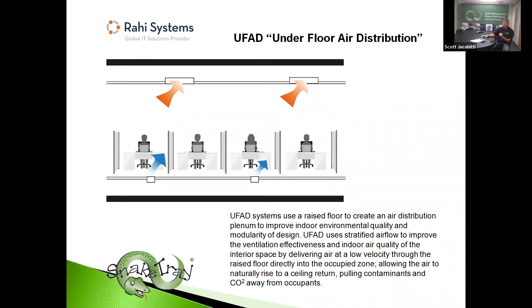The sustainability of an underfloor air delivery system improves energy efficiency. In the old way, I'm pumping high pressure cool air, say 50 degrees, into the office space. As it goes down the air column it heats up, and I finally get down to the user area at 70 degrees. In a raised floor environment, I'm only pumping it in at low pressure and at 60 degrees, so there's a huge delta in the cost of heating and cooling the spaces. For all intents and purposes, it's a much healthier indoor environmental quality because there's not as much mixing going on.